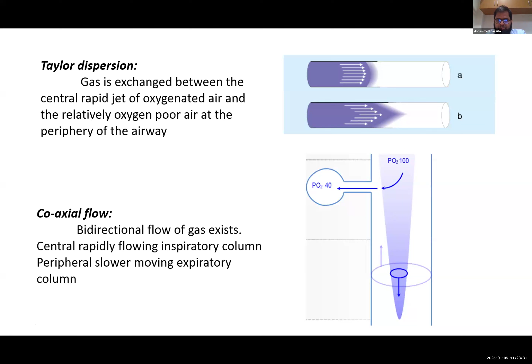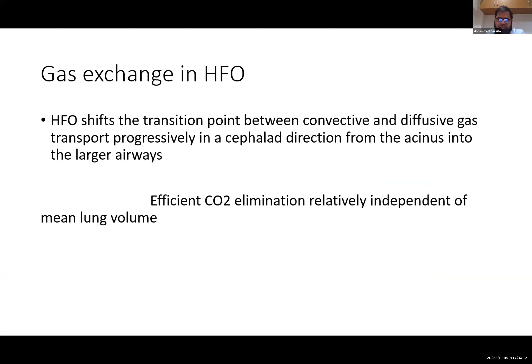Basically, gas exchange in HFO shifts the transition point between convective and diffusive gas transport progressively in a cephalad direction from the acinus into the larger airways. In conventional ventilation, gas exchange happens mainly in the acinus, but in high frequency ventilation it happens in the acinus and also in the larger airways. So more areas are involved, and there is more efficient CO2 elimination, relatively independent of the mean lung volume. Though we are giving a very small tidal volume, gas exchange happens even in the larger airways, which explains the better CO2 elimination.